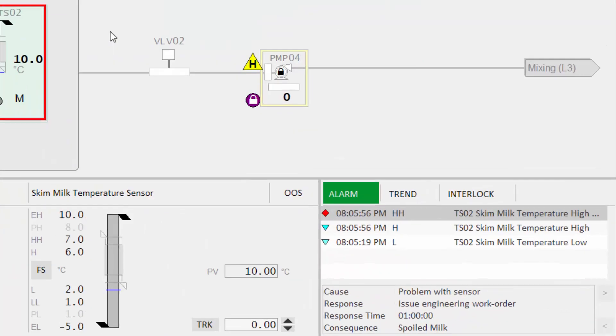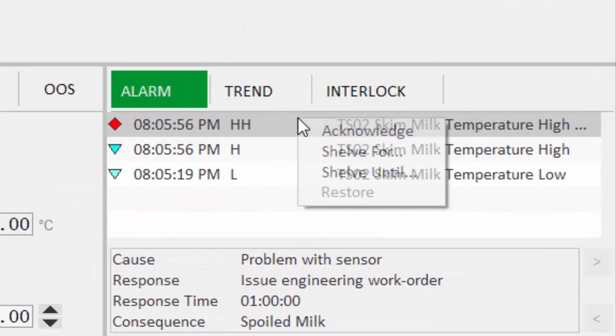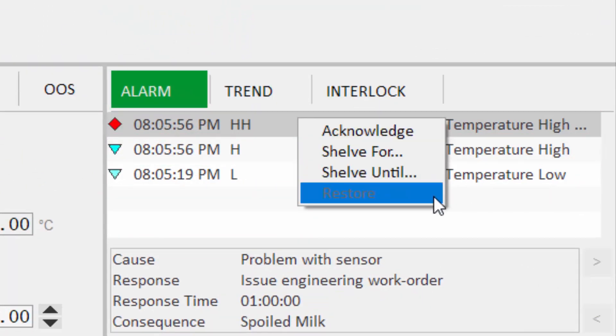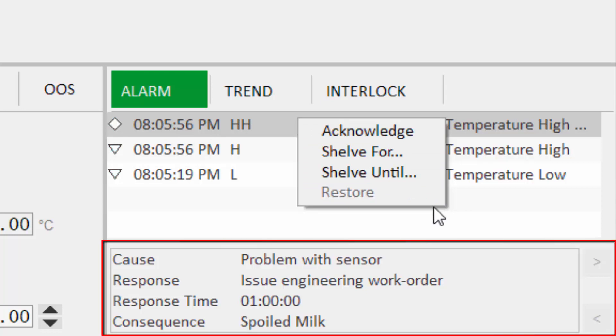Looking closer at the information zone, we can see this provides direct access to alarm acknowledge and shelving functions right out of the box. We also have a dedicated area to display the potential causes for the selected alarm and the suggested response for the operator, helping to provide tailored guidance to diagnose and respond to abnormal situations.